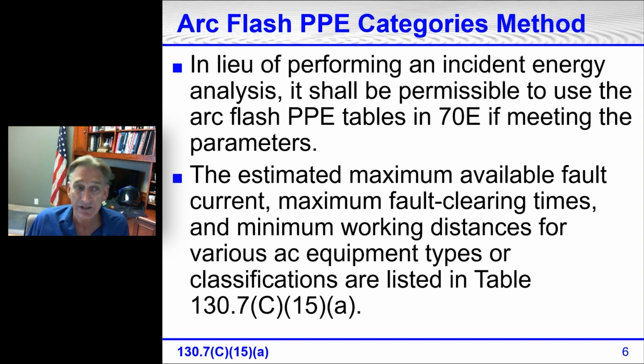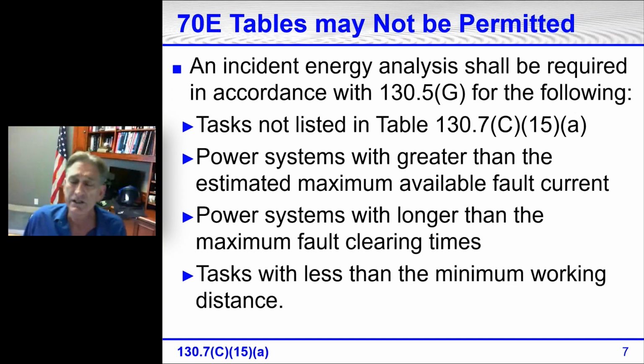Instead of performing an incident energy analysis, it is permissible to use the arc flash PPE category tables in 70E if you're meeting the parameters. We'll talk about those: the estimated maximum available fault current, the maximum fault clearing times, and the minimum working distance for various AC equipment types or classifications are listed in table 130.7C15A. We'll see these tables in a few minutes. So you can use the tables in 70E, but in using them, you have to be within the parameters. Well, what are the parameters?